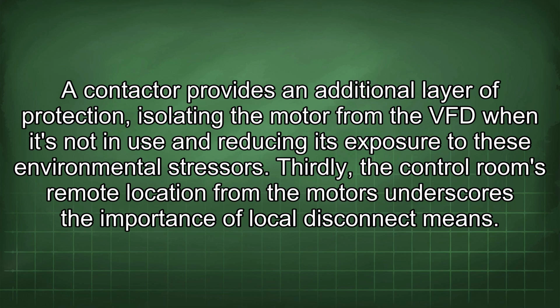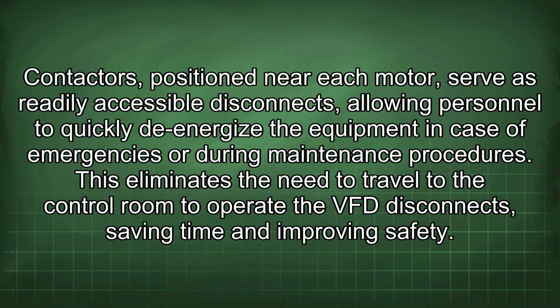Thirdly, the control room's remote location from the motors underscores the importance of local disconnect means. Contactors, positioned near each motor, serve as readily accessible disconnects, allowing personnel to quickly de-energize the equipment in case of emergencies or during maintenance procedures. This eliminates the need to travel to the control room to operate the VFD disconnects, saving time and improving safety.